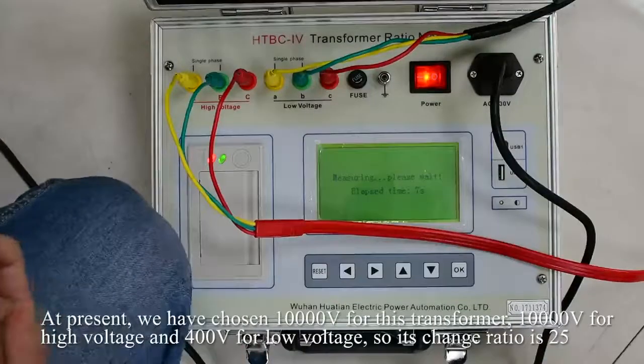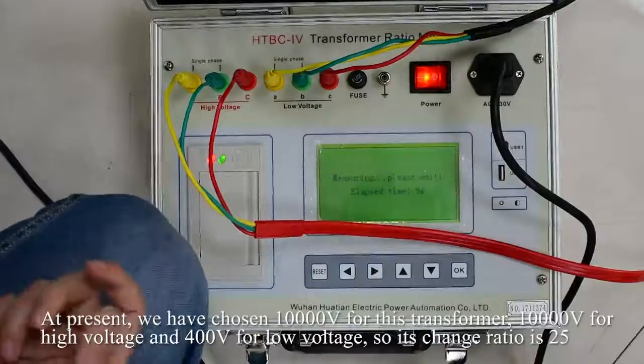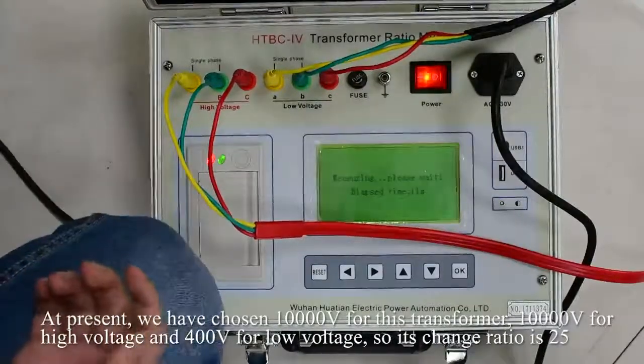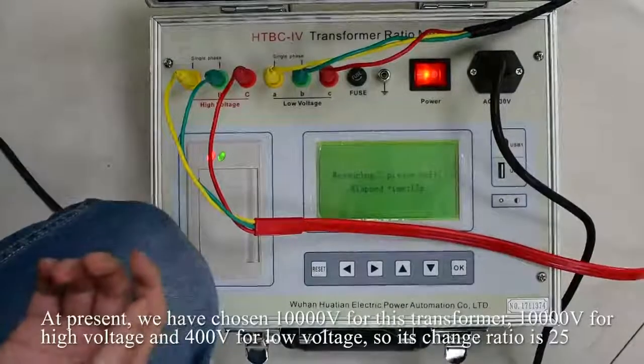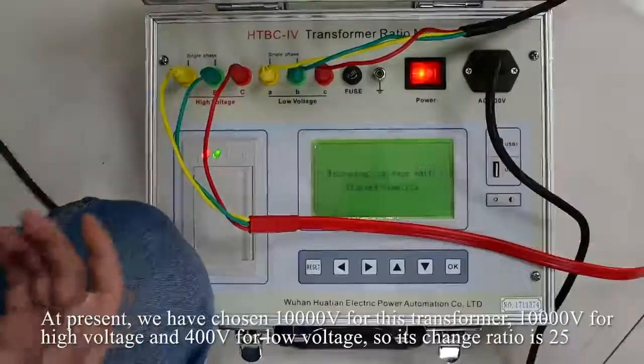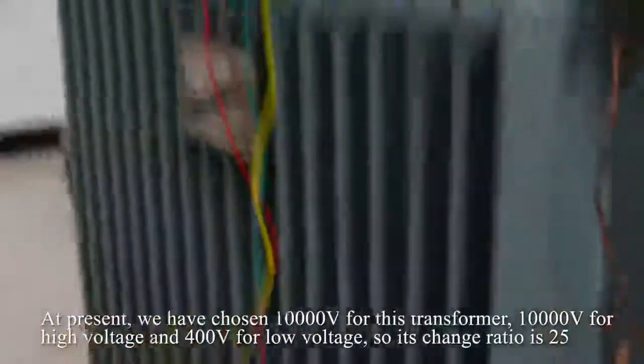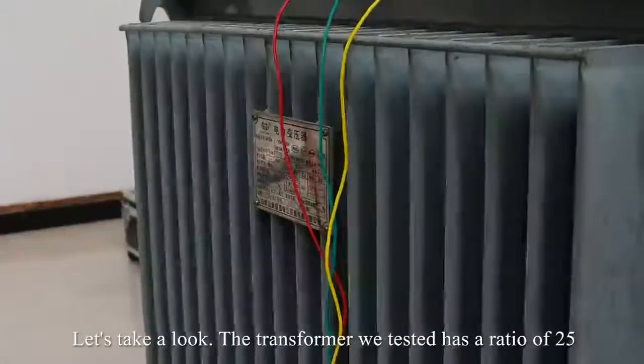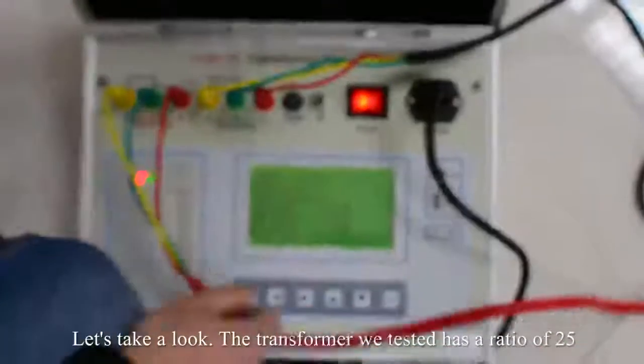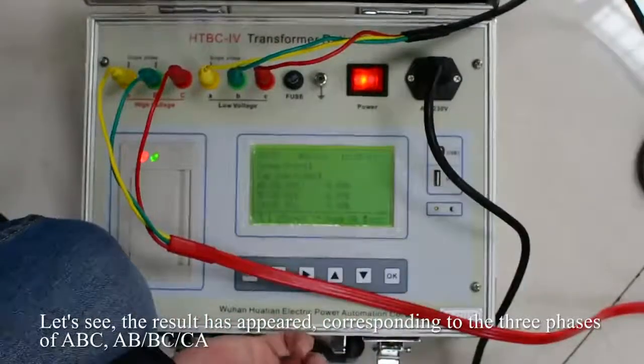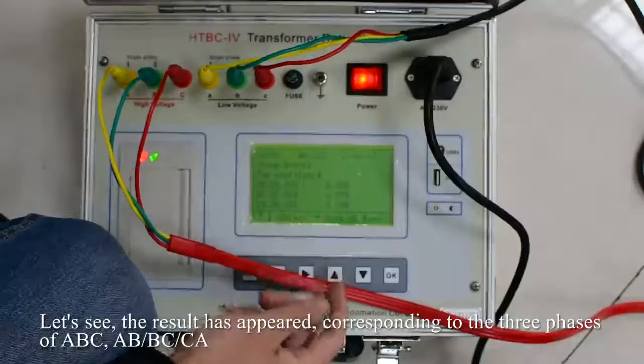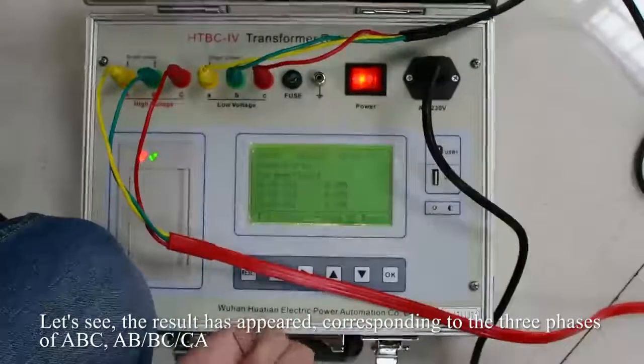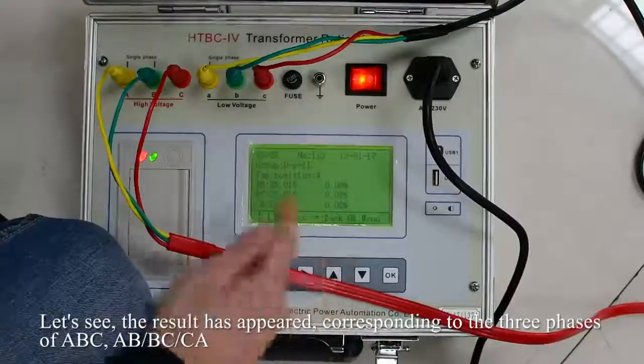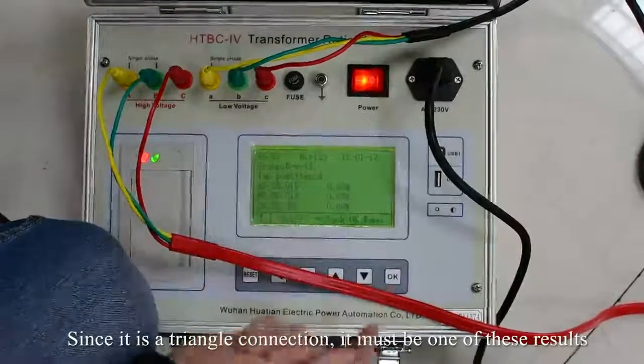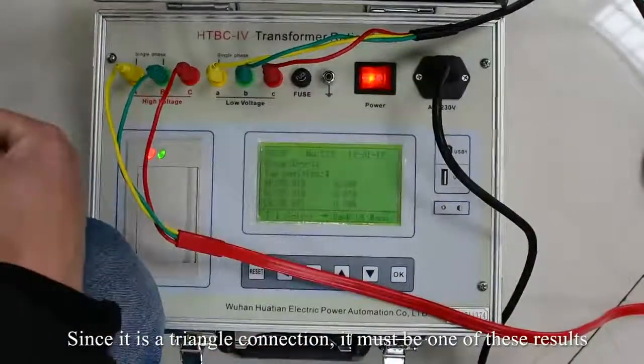At present, we have chosen 10,000 V for high voltage and 400 V for low voltage for this transformer. So, its change ratio is 25. Let's take a look. The transformer we tested has a ratio of 25. Let's see. The result has appeared, corresponding to the three phases of A, B, C. AB, BC, CA. Since it is a triangle connection, it must be one of these results.